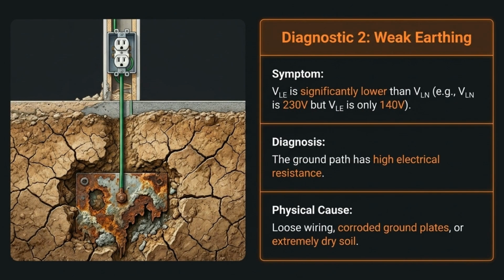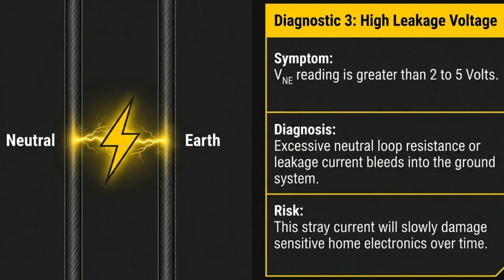Diagnostic 2. Weak earthing. VLE is significantly lower than VLN, indicating high electrical resistance in the ground path. This can be caused by loose wiring, corroded ground plates, or extremely dry soil. Diagnostic 3. High leakage voltage. A VNE reading greater than 2 to 5 volts suggests excessive neutral loop resistance or leakage current bleeding into the ground system. This stray current risks damaging sensitive home electronics.